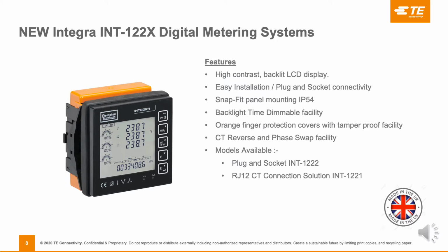The facility on the display has a backlight time which is dimmable, so after 10 seconds or up to 120, which is programmable in the unit, the backlight fades and it re-energizes once you press the button, so it lights up again. Orange finger protection covers with tamper-proof facility are supplied as standard, which we'll go into in more detail, and also has the facility to reverse the CT connections on the 1222 product and swap phase 1 to phase 3 around, depending on the outgoing way on the Integra 1221. Two models available. As I said, the plug and socket is the 1222 and the RJ12 is the Integra 1221. We will go into more detail on that shortly.